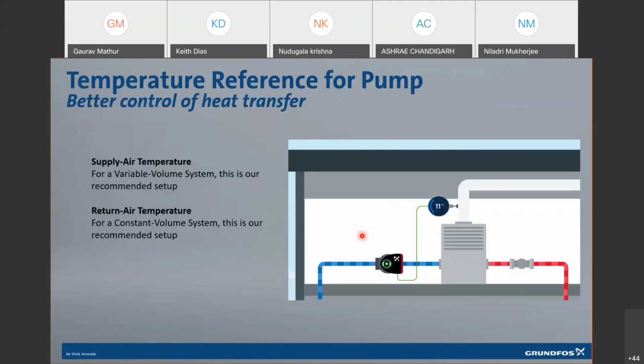The other areas where you look at the saving coming from, we will touch upon the savings aspect, both in terms of CapEx and in terms of OpEx. But let's look at the controls part, which we discussed right in the beginning, that you have a temperature-based control for the pump which is connected with the AHU. So this is basically an air temperature sensor. You can connect it with the pump and you can put the set point in the pump for the temperature requirement. You can have a supply air temperature or a return air temperature. Our recommendation is that if you have a variable volume, you should go for a supply air temperature. If you have a constant volume, you should go for a return air. But then it is as per your design, you can let us know. Either way, we can put the set point in the pump and run the pump as per the requirement.